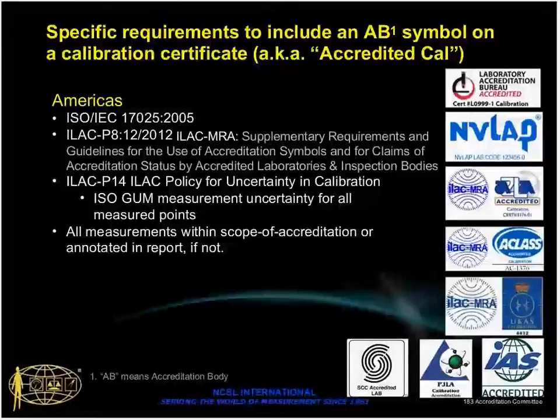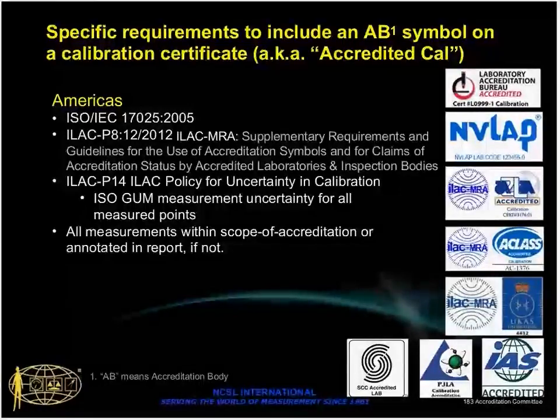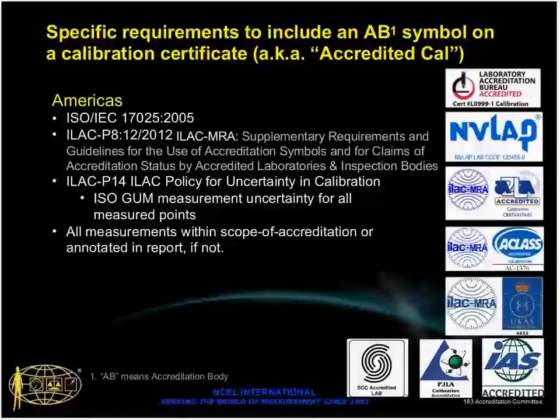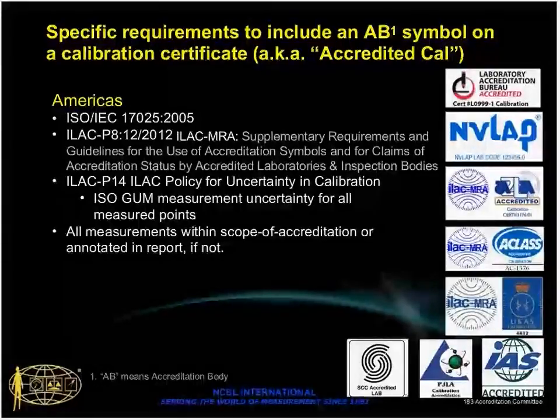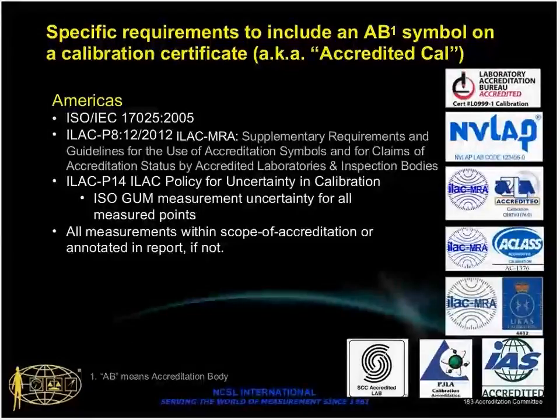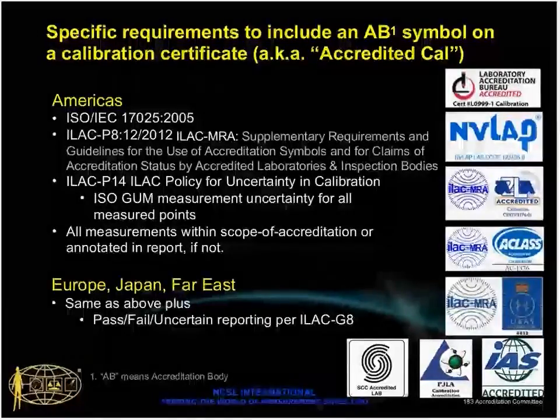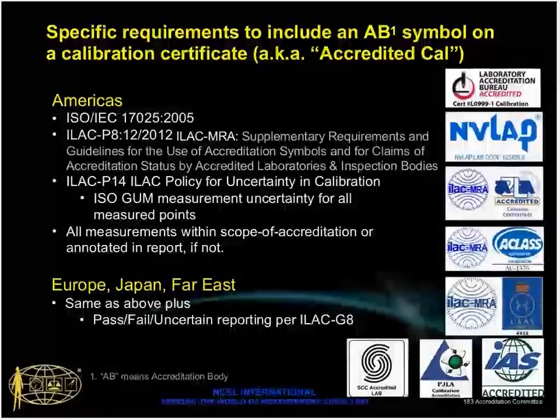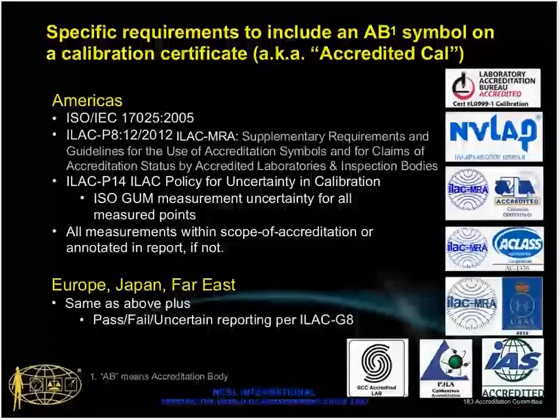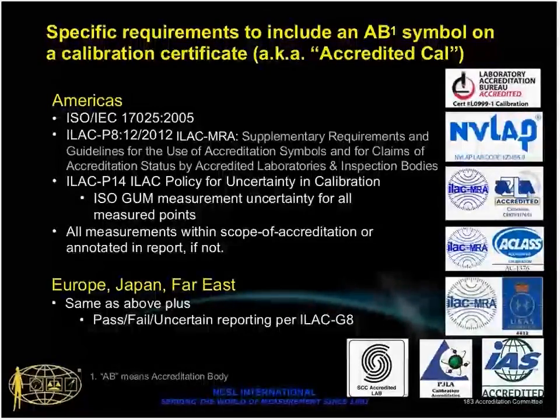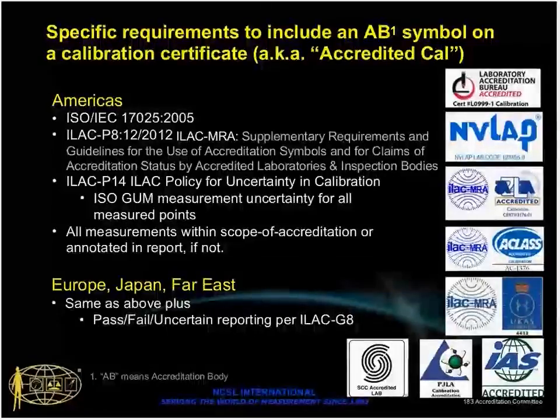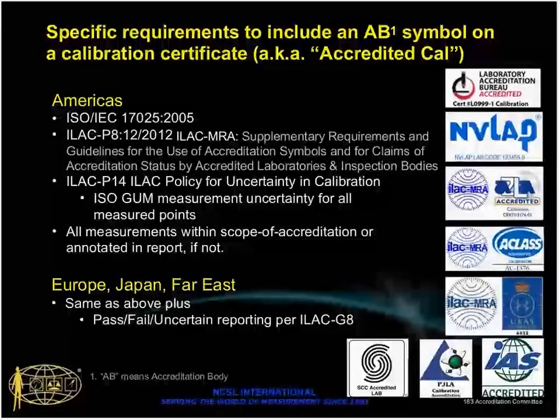But also we have ILAC P14. ILAC P14, of course, is the policy for the uncertainty in calibration. Inside that policy, it describes how the uncertainty is to be reported, following the guidelines for the expression of uncertainty of measurement. But when we look at the measurements themselves, we have to make sure that the measurements are within the scope of accreditation. If they're not, we have to segregate them somehow and identify them as not being part of the scope.